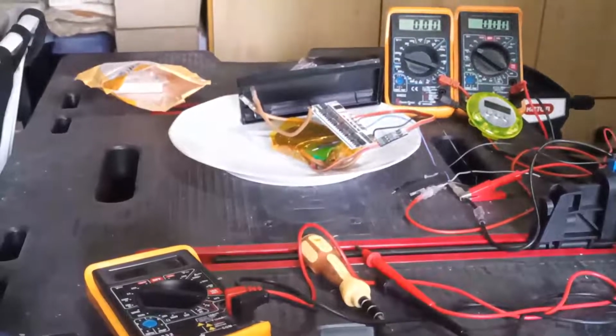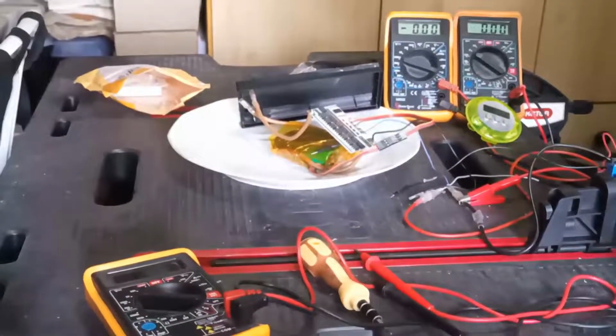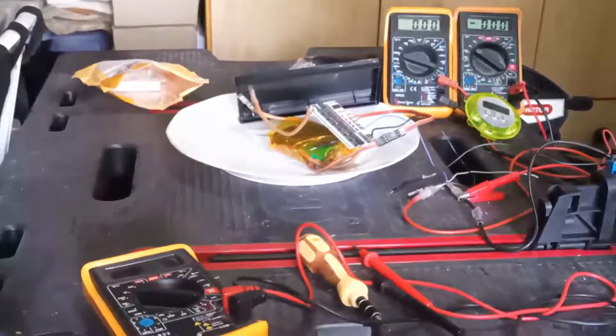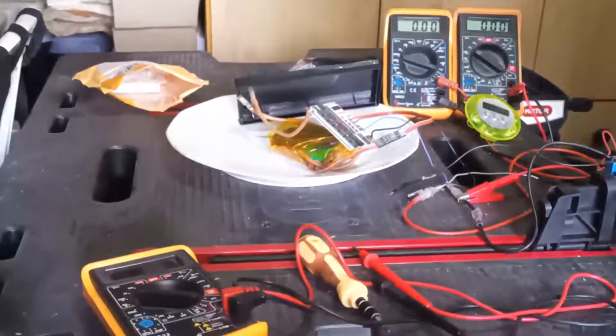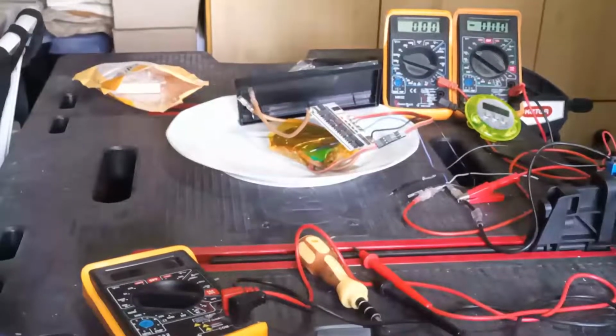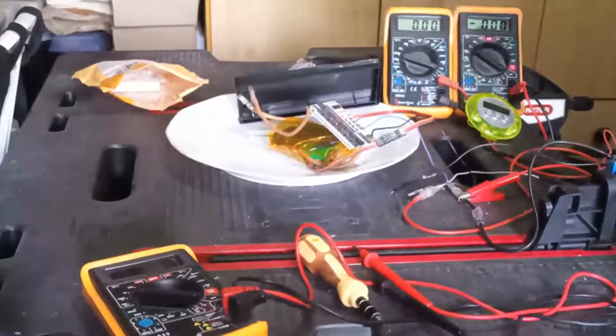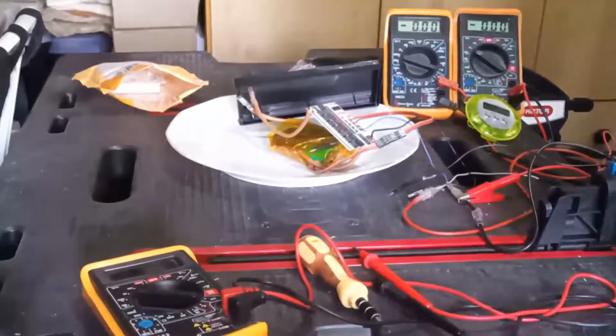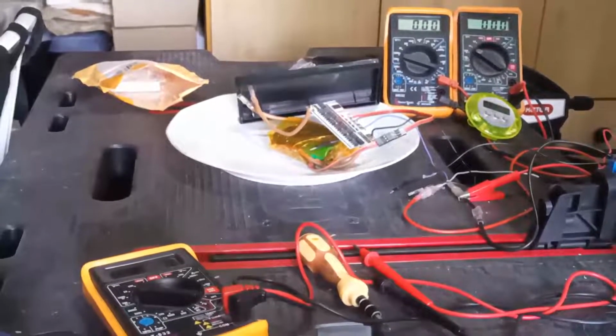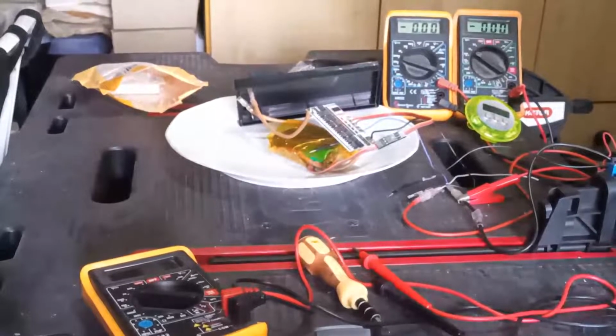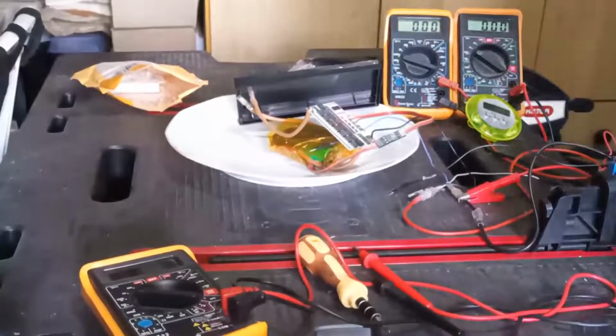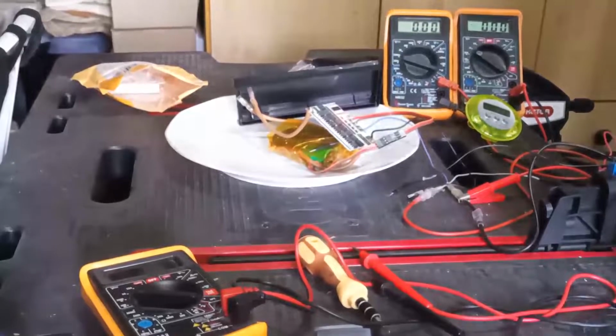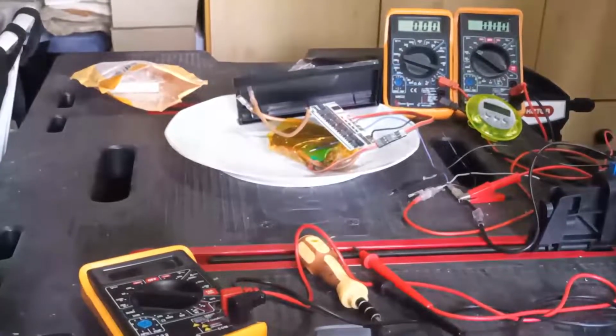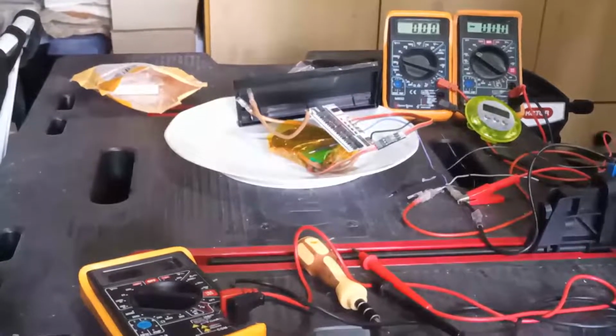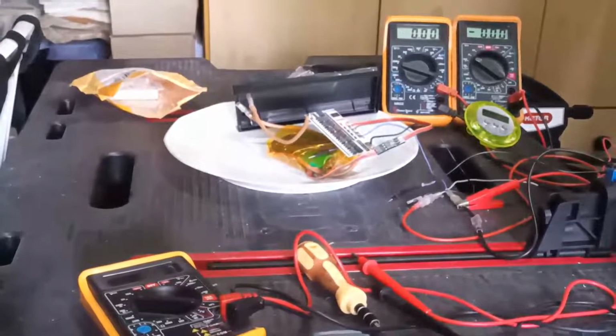So the cells will continue to gather charge until they overcharge and the voltage goes above 4.24 volts, and we are supposed to see the BMS cutting the current off. Of course, the voltage we'll read here will be slightly higher because we're reading from the charger side, but still we are supposed to see the BMS cut off. The cell is supposed to explode at not less than 4.4 volts, so we have a lot of time to stop it if it doesn't happen, but the principle of operation is that the BMS needs to cut off the current if the cells, or one of them, get seriously into overvoltage.